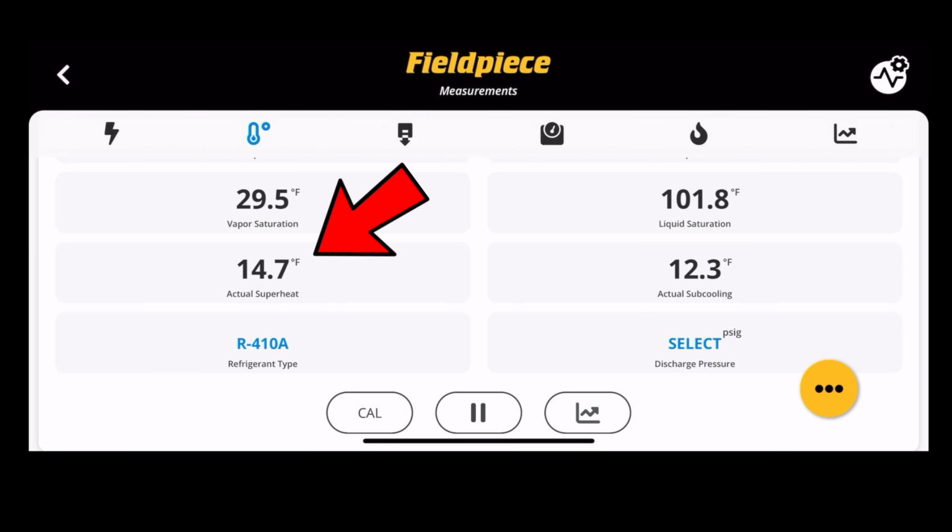And also, that's a 4-ton blower, so it's only capable of moving up to 1600 CFM. That's a 5-ton condenser. So at some point, it looks like the blower coil inside is the original setup, and then the outdoor unit's been replaced at some point. And when they did, they probably just upgraded to a 5-ton and didn't adjust for the inside.